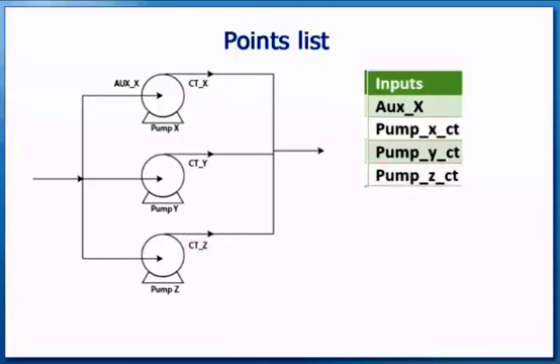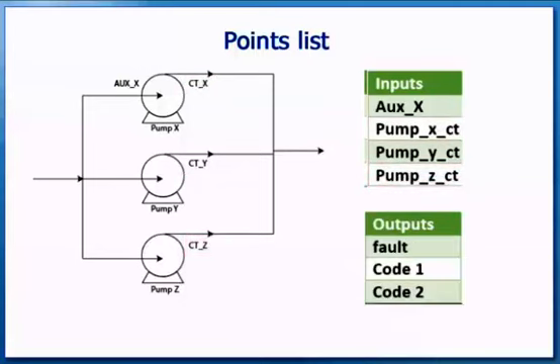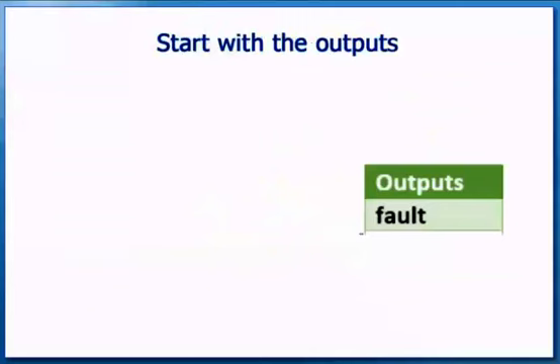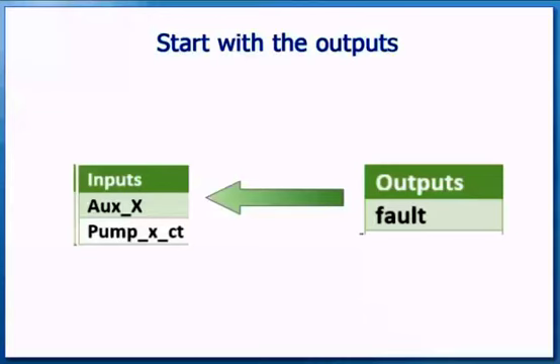There are three digital outputs. The first is Fault, to indicate when PUMPX is in a fault condition. The next two are code bits that can indicate how many pumps are running. Divide the whole project into a series of smaller tasks by dealing with one output at a time. Start with the outputs and work back to the inputs by deciding what has to happen for the output to come on.